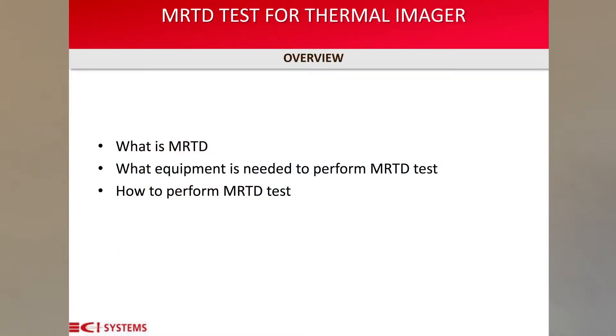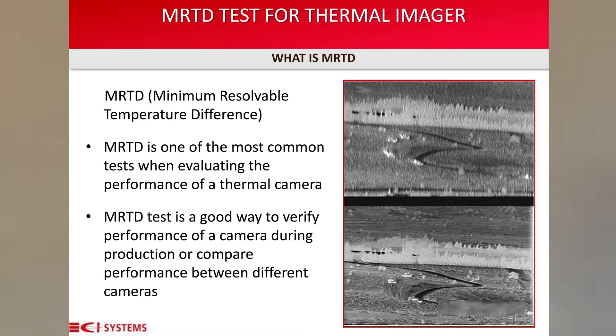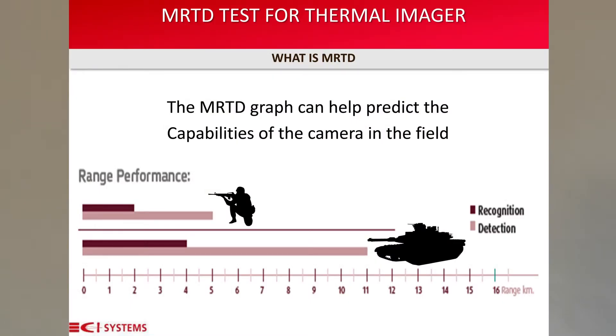What is MRTD? What equipment is needed? And how to perform the MRTD test? MRTD stands for Minimum Resolvable Temperature Difference. It is also known as MRT. MRTD is a test that helps us evaluate the performance of a thermal camera. It enables the user to estimate the performance of the camera in the field by measuring the probability of detection, recognition, and identification of a target in the field. MRTD is a subjective test because its output is based on the user's ability and not on image processing.